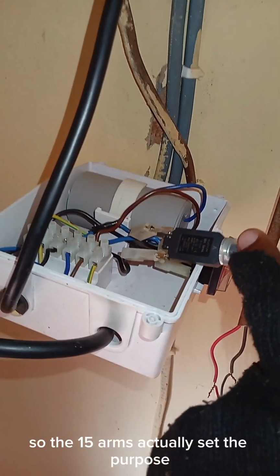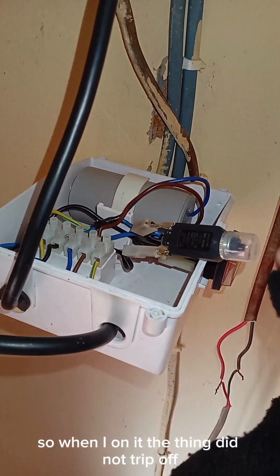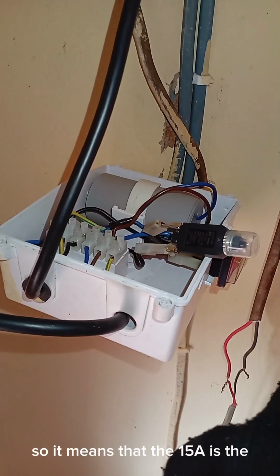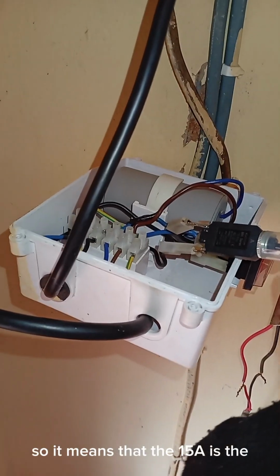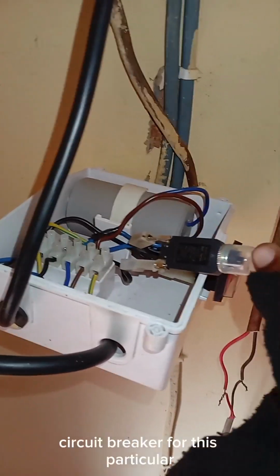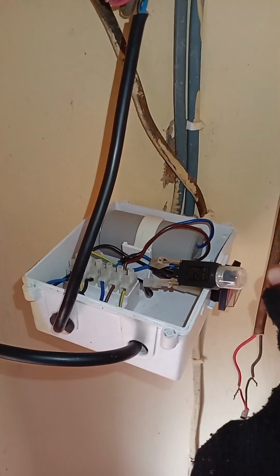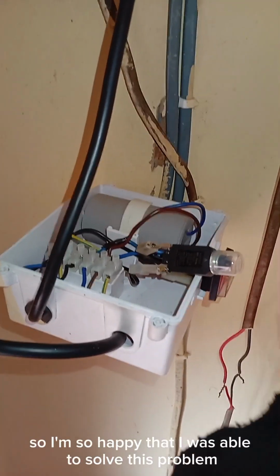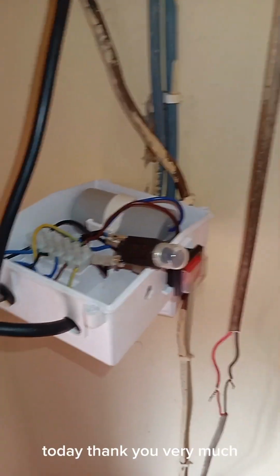So the 15 amps actually served the purpose. When I switched it on, the thing did not trip off. So it means that the 15 amps is the correct rated circuit breaker for this particular submersible pump. I'm so happy that I was able to solve this problem today.